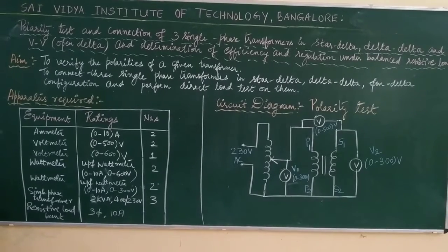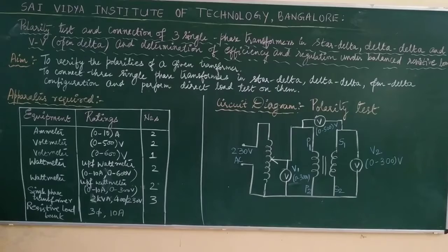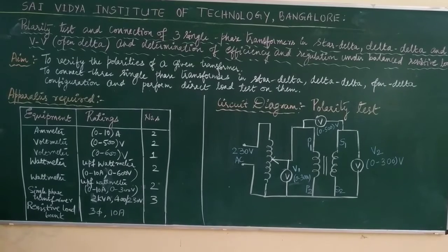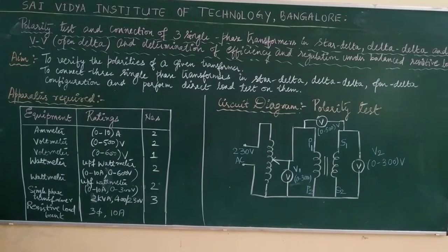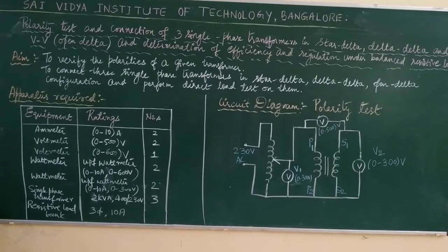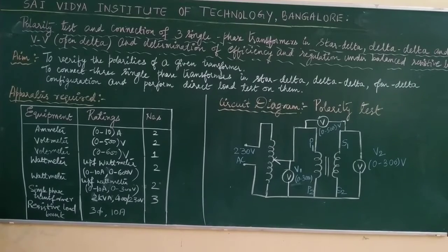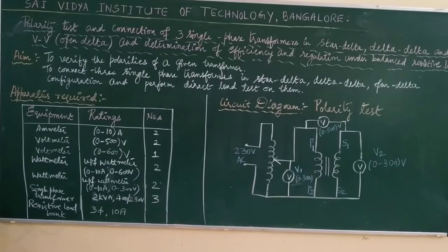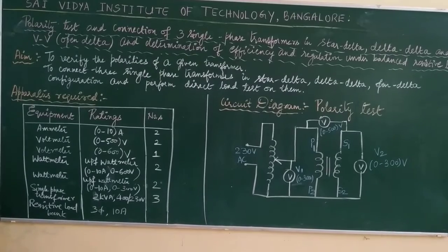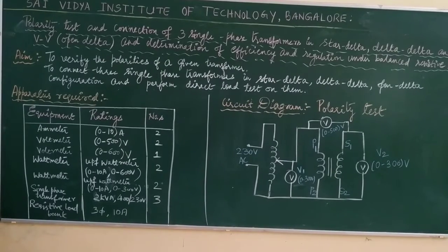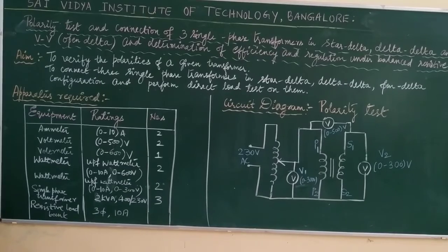Polarity test will be mandatory in order to connect any two transformers in parallel. The second part of the experiment is to connect 3 single phase transformers in bank configuration to get star delta, delta delta and open delta configuration, and then perform direct load test on them. So let us go to the apparatus required.